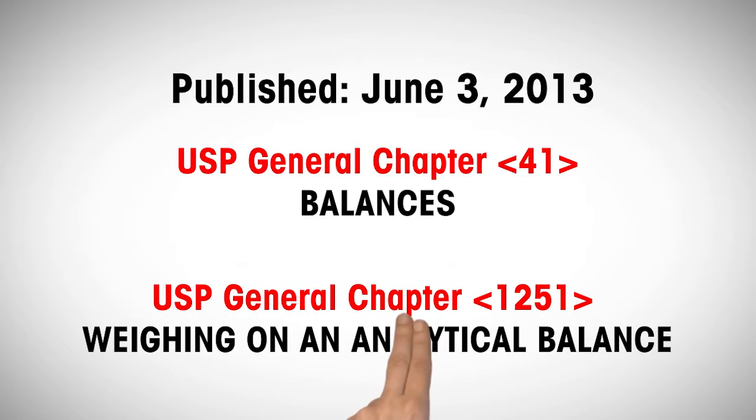On June 3, 2013, the United States Pharmacopoeia published a second supplement to the USP 36 National Formulary 31. This video informs you about the relevant changes in the general chapters about weighing, namely USP General Chapters 41 and 1251, which will be official on December 1, 2013.